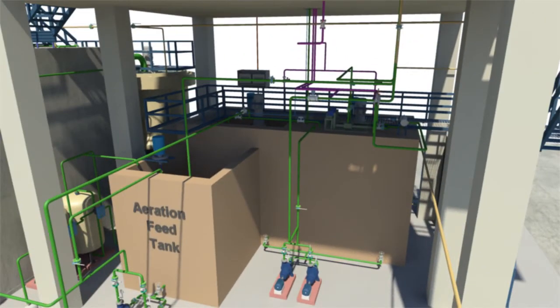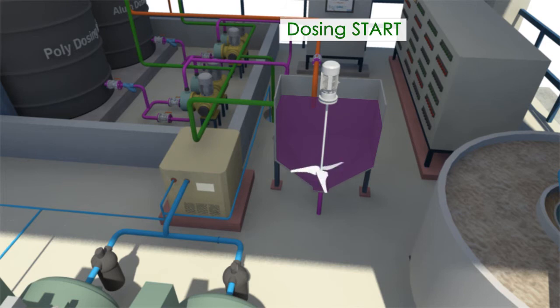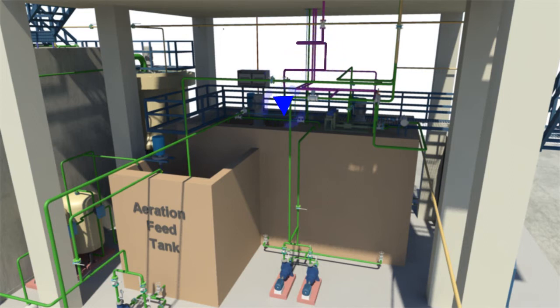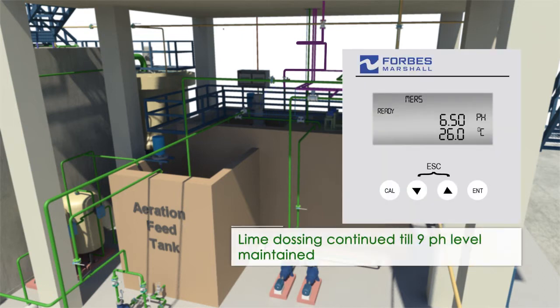The alum dosing pump stroke setting will have to be manually adjusted based on a regular daily jar test to establish the required alum dosage. The alum pump start will be automatic after the lime pump. This dosing is sequential as per the filling sequence of the tanks, and dosing continues until the pH level reaches 9.0, which is maintained throughout the operation.